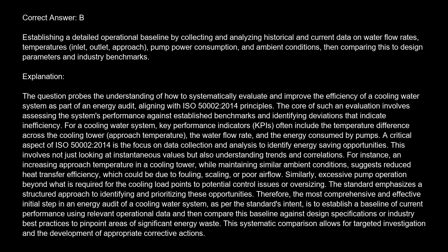For instance, an increasing approach temperature in a cooling tower, while maintaining similar ambient conditions, suggests reduced heat transfer efficiency, which could be due to fouling, scaling, or poor airflow. Similarly, excessive pump operation beyond what is required for the cooling load points to potential control issues or oversizing. The standard emphasizes a structured approach to identifying and prioritizing these opportunities.